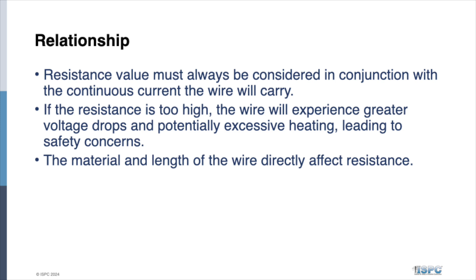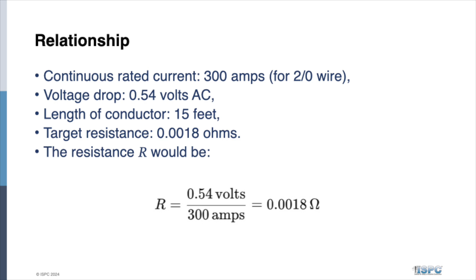So you can see here, this is just strictly the resistance value of that temporary ground, right? You can see the ohm value that you get there, all right? So voltage divided by the available 300 amp current, there's where you should be if you just went across it with a voltmeter, okay? Obviously we don't test our grounds like that, right? Bierer Meters has a ground tester, and they apply current to that ground and then take a reading, right, to get you to a satisfactory value.